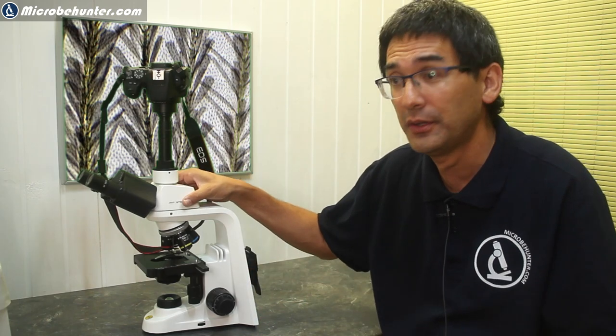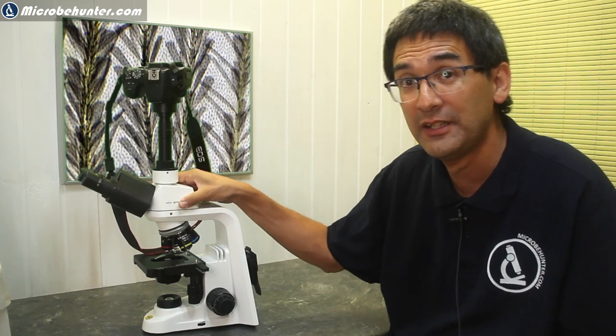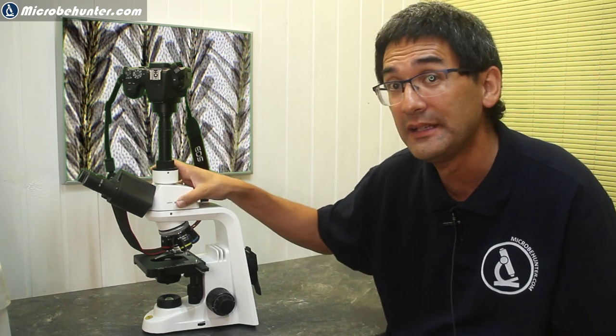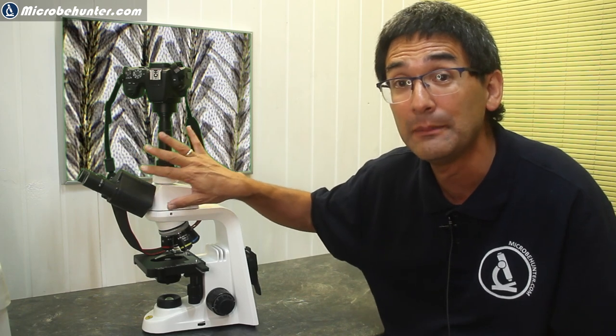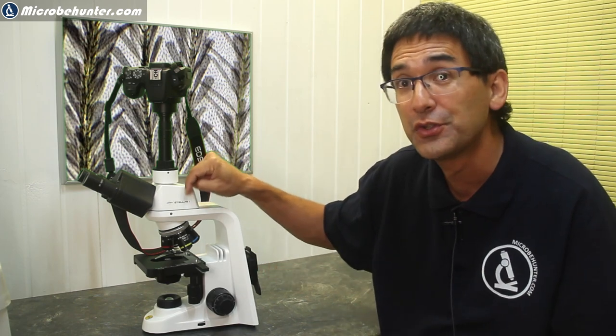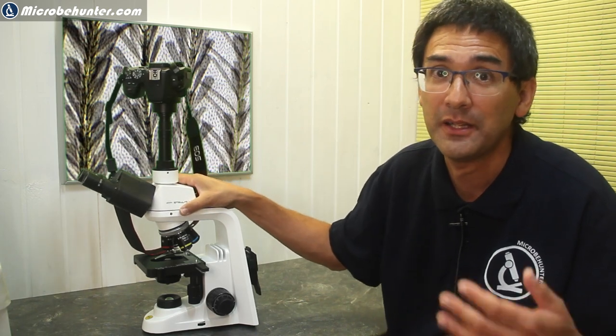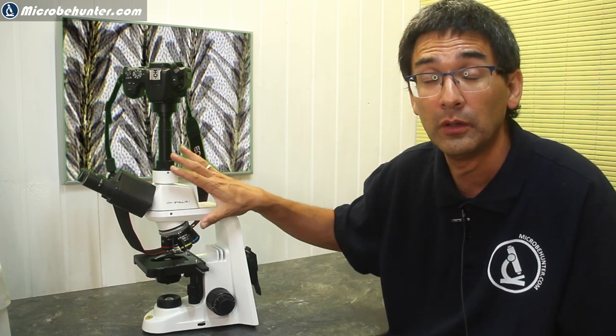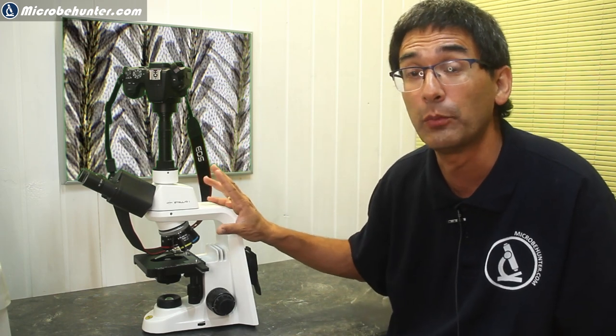So now what are some of the things that I particularly like about this microscope? Well, first of all, I like the overall very good mechanical quality of the device. Like I want to give you an example. When you turn the trinocular head here, it goes very smoothly. And there is no scratching. And the reason is that the screw over here that holds the microscopy head, the trinocular head in place, the screw itself does not scratch the dovetail. There is actually a bearing system in here that allows it to be turned here without actually damaging the dovetail. So I like this a lot. I also like generally the overall quality of the build quality of the microscope, the materials used. Most parts of the microscope are in metal. Well, that is to be expected anyway, but even those parts that you normally do not expect, for example, the base right now, which I cannot show you quite easily on the very bottom, I've actually seen, you've seen a picture before of where I accessed the LED. Even that part is made of metal, because in most cases, other microscopes, this part is plastic, but not here.